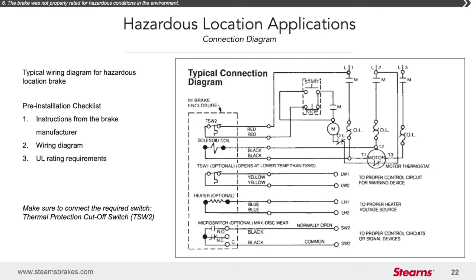One of the requirements UL places on both Division 1 and Division 2 hazardous location brakes is that each one has a thermal protection cutoff switch. I've talked to people out in the field oftentimes who told me that these things weren't even connected. Now, that right there will nullify your UL recognition, and it will nullify the hazardous location rating. So you want to make sure you have your installation instructions for the manufacturer, your wiring diagram, and that you're following all UL rating requirements.